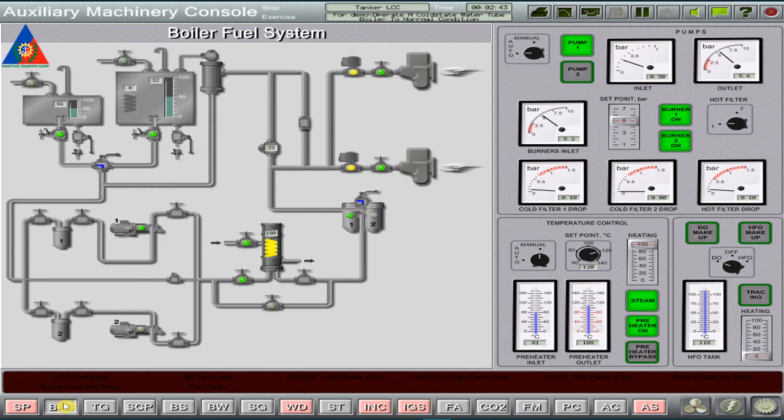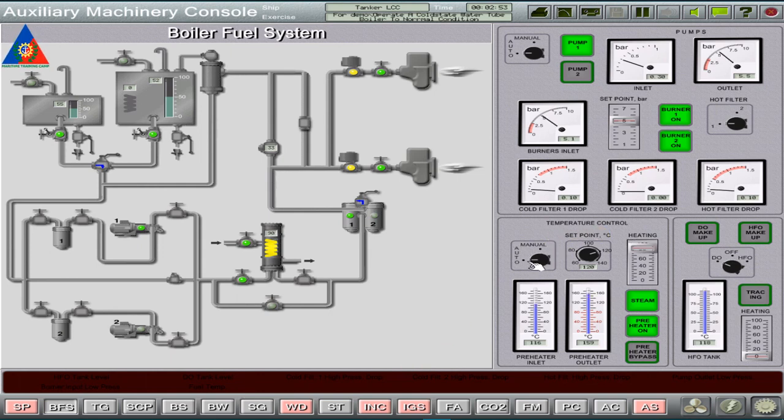Heading back to the BFS page, the fuel temp alarm has been cancelled out. But we need to set the fuel heater system controller to auto to maintain the boiler fuel temperature at 120 degrees centigrade.